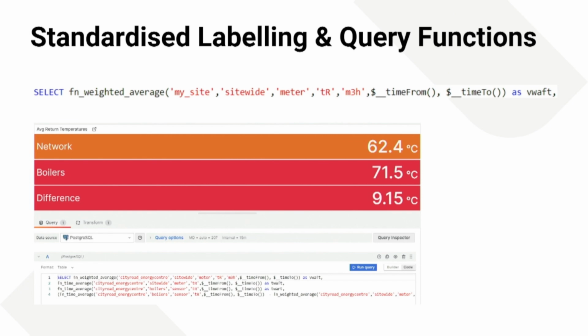Take the function for weighted average - how do you calculate the volume weighted return temperature? You pop it into this function, tell it you want that for your site, the site-wide heat meter return temperature, weighted on the flow rate, and this is what you get out the other end. You just type that in as your function and the software gives you this.